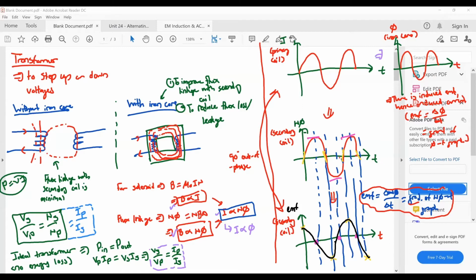It cannot flow into the primary core or the secondary core because they are all electrically insulated from each other. The wires have plastic covering, like the wires in your lab. If you coil it around an iron core, they make no electrical contact. So the iron core has induced current, but it won't flow to the primary or secondary core, it just keeps flowing inside the iron core, causing heat, which dissipates away. The energy for that heat dissipation comes from the power of the transformer itself. That's one source of power loss.